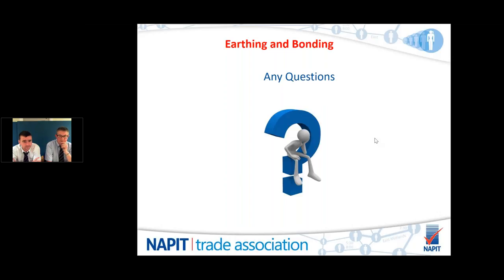Right, so final one we've got from Daniel. What would be your action if you changed a consumer unit in a block of flats which was fed in 16mm T&E with a 6mm CPC fed from a BS1361 type 2 fuse? A note on the certificate mentioning this, and apologies if that's too complicated to answer, guys. Sounds to me like the earthing conductor, or the main earthing conductor, won't be the right size. So, again, it needs a risk assessment as to whether the CPC within the 16mm twin and earth would be big enough for a start. It probably wouldn't. It probably wouldn't be big enough either for the bonding being connected to it at the earthing terminal within the new consumer unit. So the tails would probably need to be upgraded. It will also depend on how they're installed, whether they require SCDs at both ends and giving you discrimination problems. So it can be a bit of a nightmare job, that one.